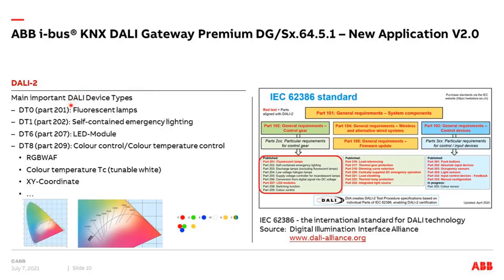DALI 2 defines several device types. Device type 0 is part 201 for fluorescent lamps, similar to device type 6 (part 207) for LED modules. Device type 1 is for self-contained emergency lighting converters. Today we focus on DALI device type 8, part 209, for color control or color temperature control — covering typical color temperature (TC), tunable white, RGB, RGBW, or XY coordinates, all specified in part 209.